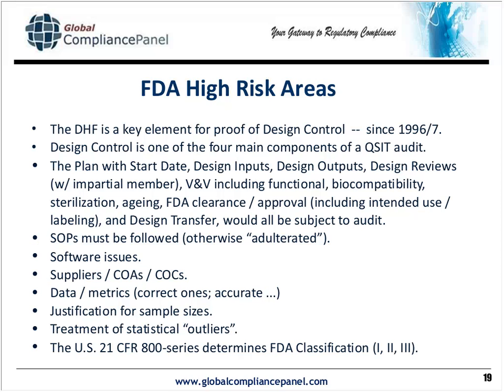Now also another key area is the recognition, and this boils down to what we talked about earlier, that the FDA product classifications like 1, 2, and 3 are different from the European Union's classifications 1, 2A, 2B, and 3, not just in the numbering, but most importantly, the FDA, if you want to classify your product, you're told by law how to do it. You have to go to 21 CFR 800 and pick up your product under there, and it'll give you the product code and the registration number for your type of product. It'll tell you what classification it is and what the FDA's expectation for documentation for it is and systems.